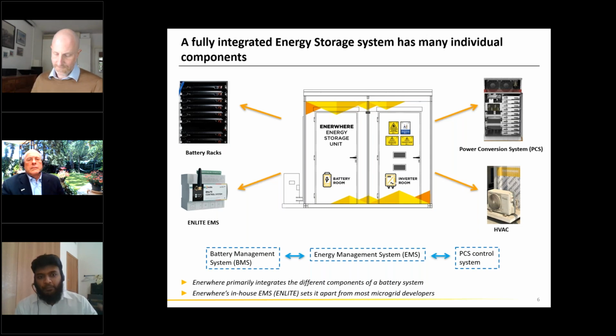So what you have is a battery rack — for people more familiar with PV, it's like putting together a bunch of battery racks, stringing them together to reach a higher voltage level, say 500 to 600 volts up to 1000 volts, giving you that battery rack module. This is a purely DC system with a battery management system on top that manages voltage balance, cell balancing, and the temperatures of the cells within that system.